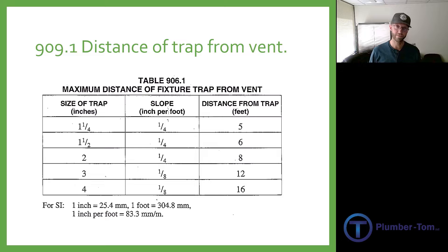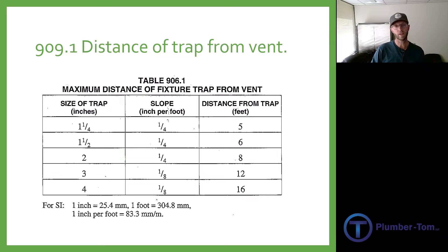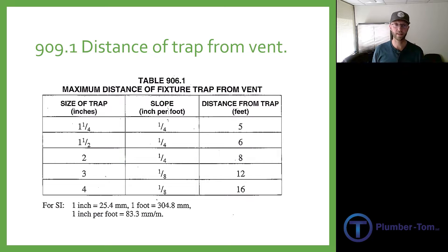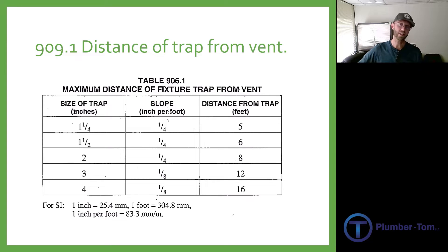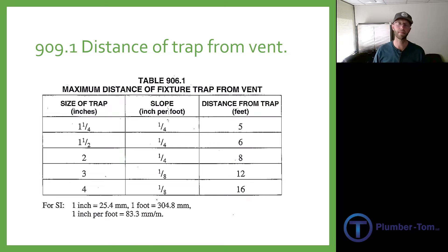Five feet for an inch and a quarter. Most common ones we'd be dealing with — you might have a one-and-a-half-inch horizontal branch coming over for a lav: six feet, that's your limit for how far you can go. What about reaching out to get a shower, coming through the floor joists with a two-inch pipe? Eight feet. Lock these in memory — it's going to be useful.